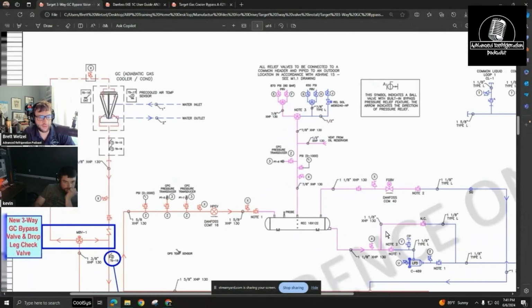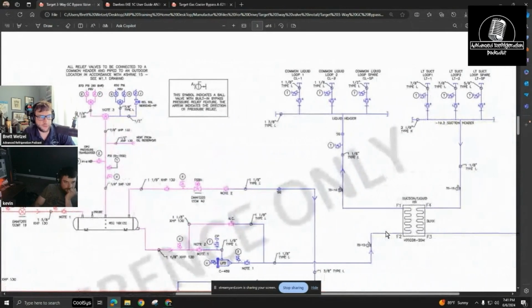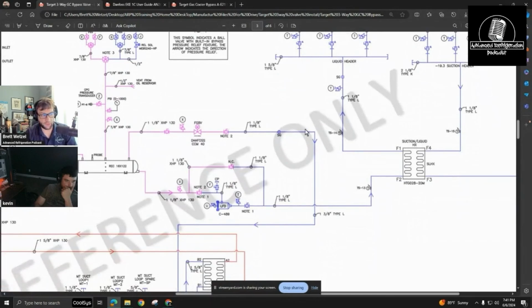So if you were to technically have some sort of isolation, like at your liquid header, and you'd close off this valve, and you wouldn't have any reliefs from here on out, and you would switch this relief over to the 870, where now it's only going to relieve when it goes up to 870. I'd think that this potentially comes into possibly getting damaged.